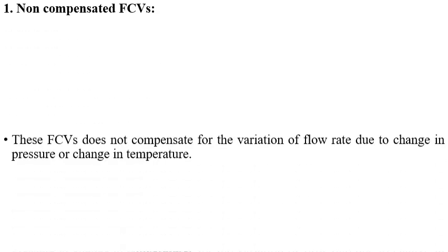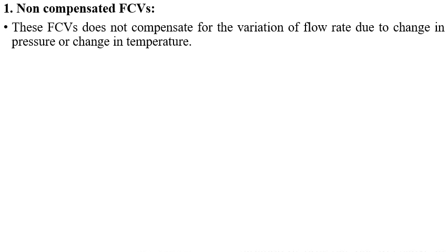The first one is the non-compensated flow control valve. It means these flow control valves do not compensate for the variation of flow rate due to change in pressure or change in temperature. As pressure varies, the flow rate also varies. Similarly, as temperature varies, the viscosity varies and the flow also varies due to the change in viscosity.